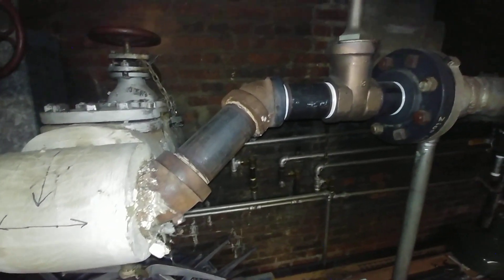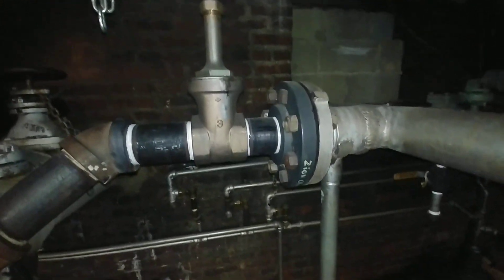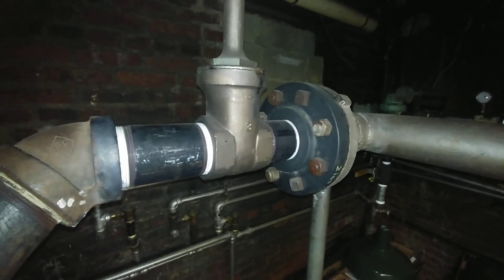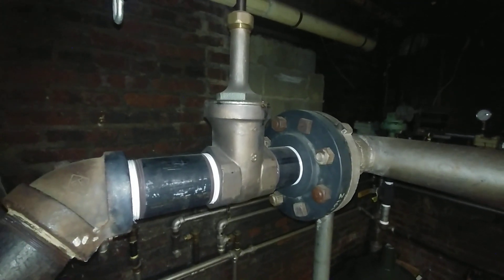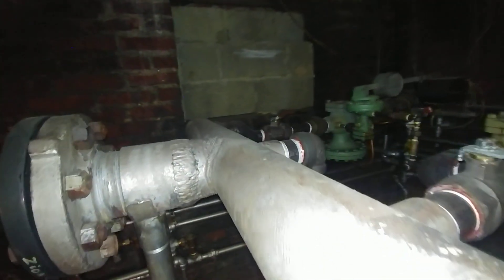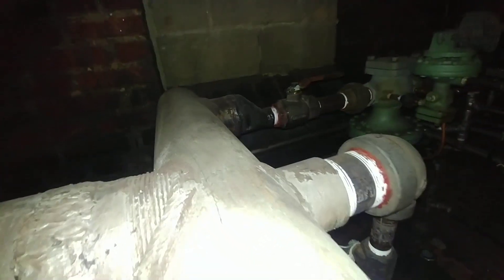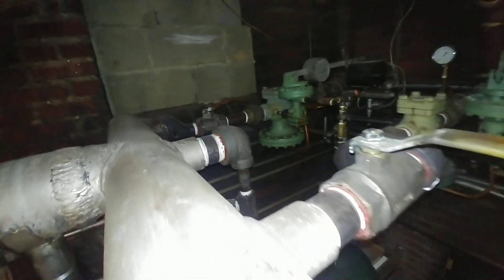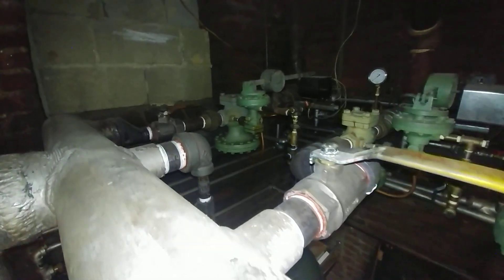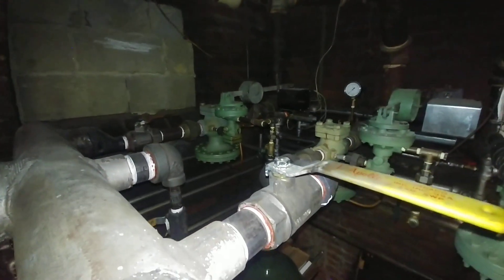This is Zion Lutheran's leg here, and that's their main shutoff valve, which failed a couple of years ago and the steam utility replaced it. And it goes into this manifold here. It's split into what used to be five zones, but now it's down to three. A lot of these zones have been abandoned, cut off, and reduced.